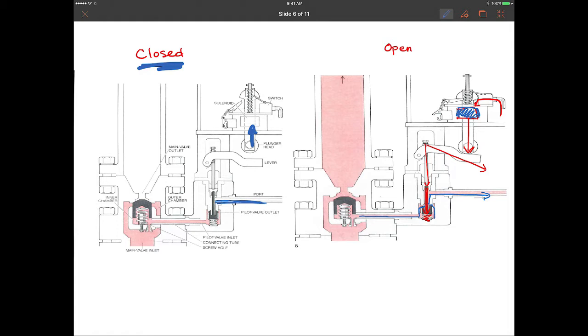So it didn't cross their mind at the time to think, wait a second, this isn't a signal of the PORV being open, this is just a signal of the solenoid being activated. They didn't understand that in their mental model. So they really didn't have a true picture of what was actually happening, and it stopped them from questioning, wait a second, maybe this thing's just stuck. I know how this works. Maybe the solenoid is activated, but the plunger head is stuck. And indeed, that's what actually happened, right? In the actual case, the solenoid was activated, but the plunger didn't depress. Okay, that's what actually happened.